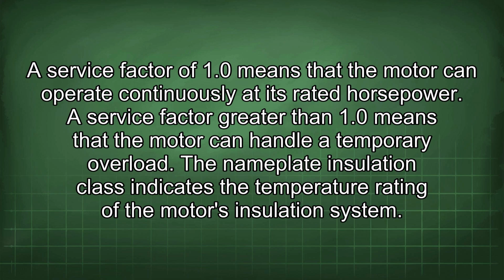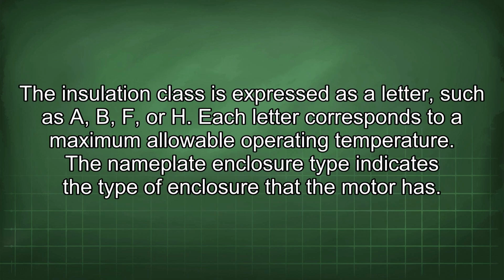The nameplate insulation class indicates the temperature rating of the motor's insulation system. The insulation class is expressed as a letter such as A, B, F, or H. Each letter corresponds to a maximum allowable operating temperature.